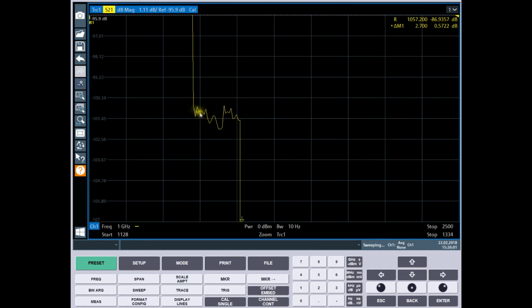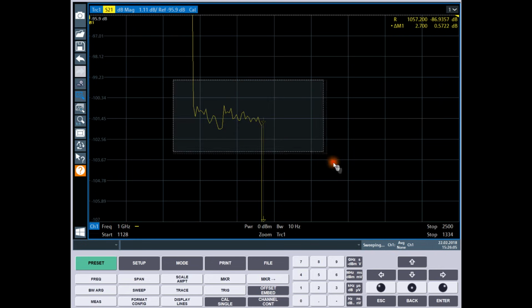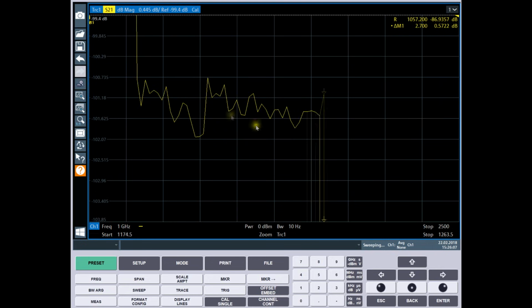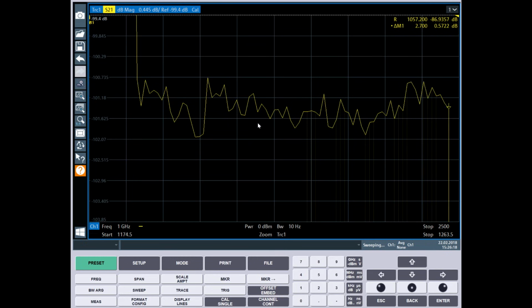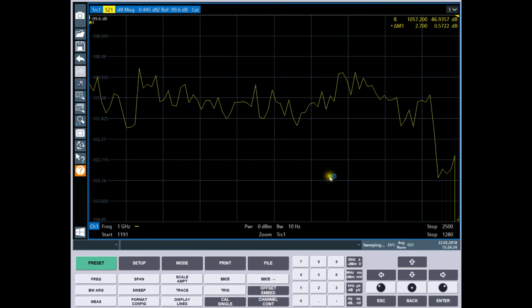And it's going to be more difficult, as you can see. Yep, it's now much harder for the instrument to give us an accurate representation of each individual step. There's just too much noise. Now, a few other things to note. I have no averaging here. The only thing I have is a 10 Hz bandwidth. I'm not using any of the math functions which would allow us to make multiple measurements and average them out. None of those is being used here. So this itself is going to limit, of course, the performance.